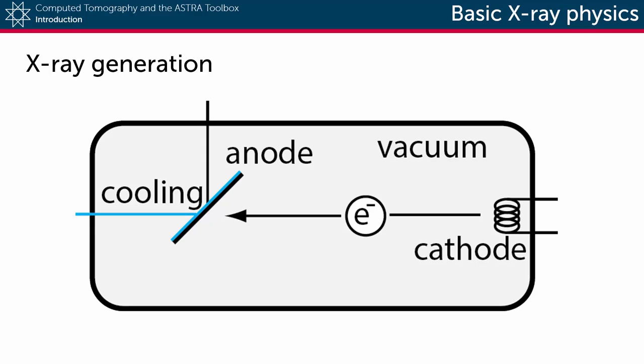As the electron interacts with atoms of the tungsten anode it will then lose its energy. Most of this will dissipate as heat so the anode has to be well cooled, but a small portion of this energy will be converted to X-rays.